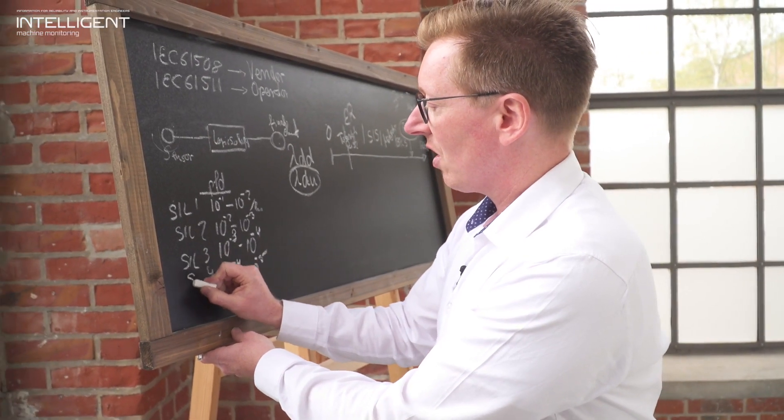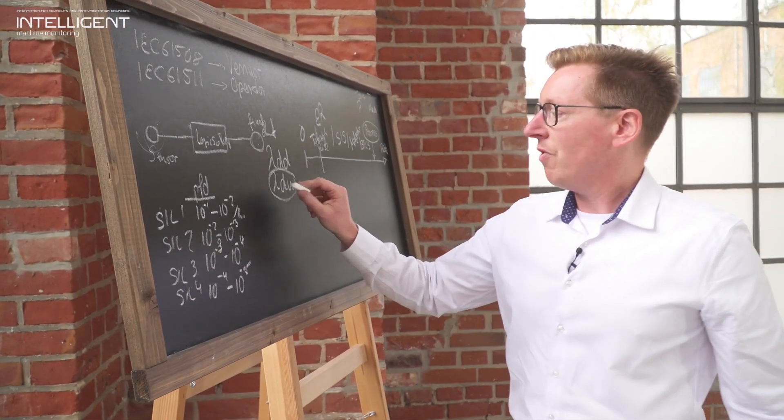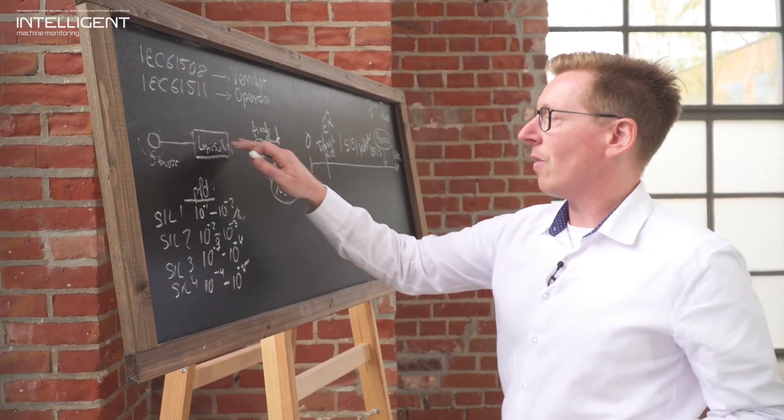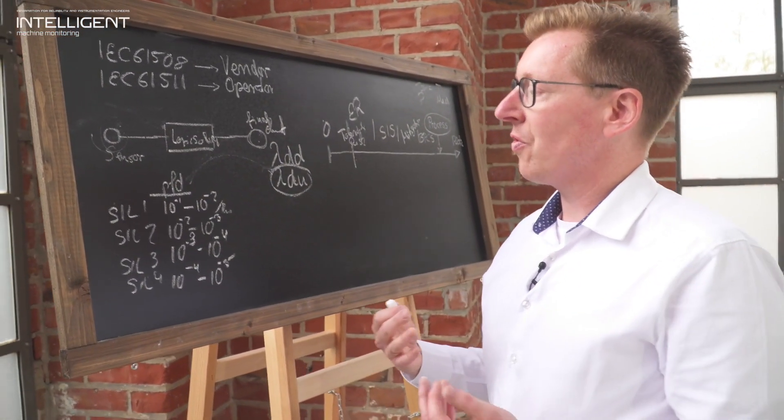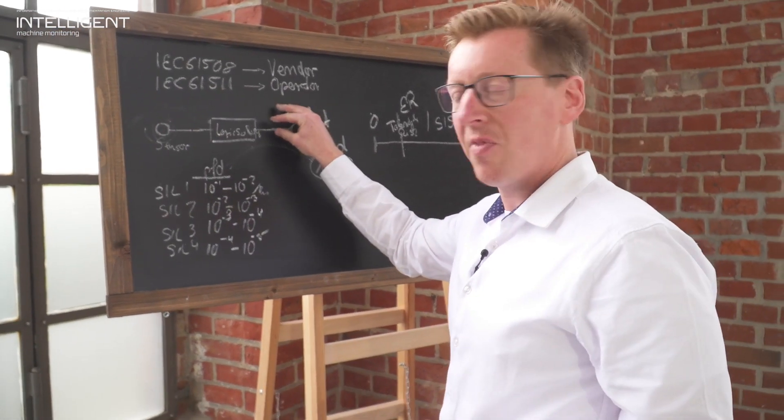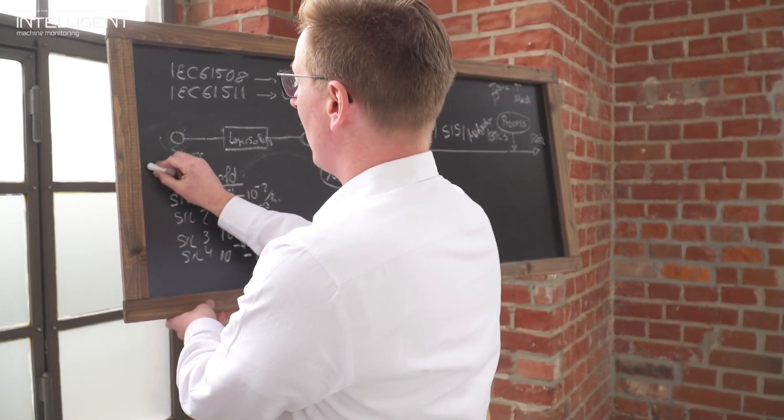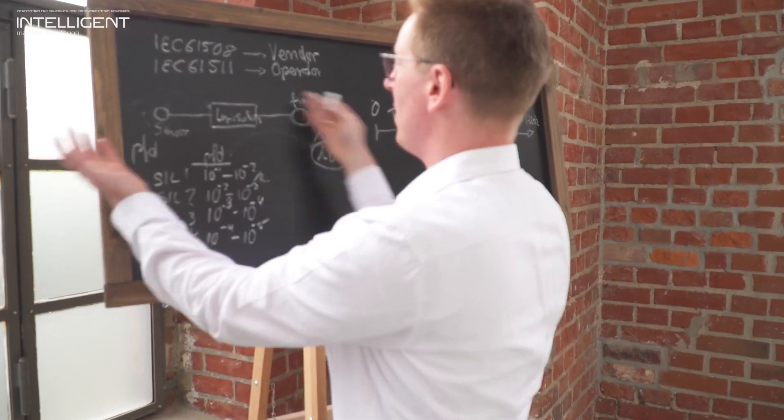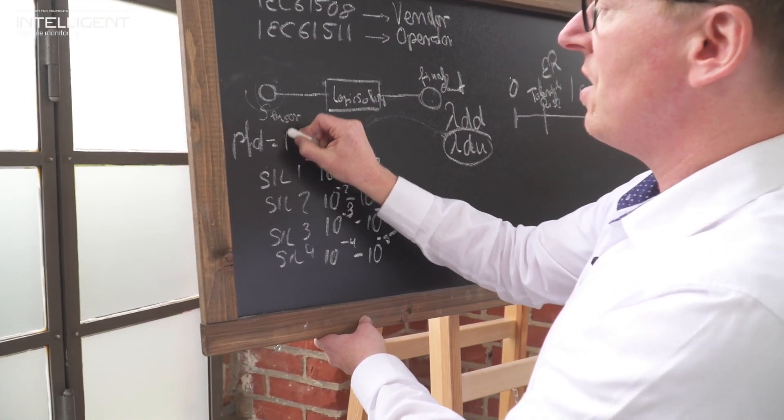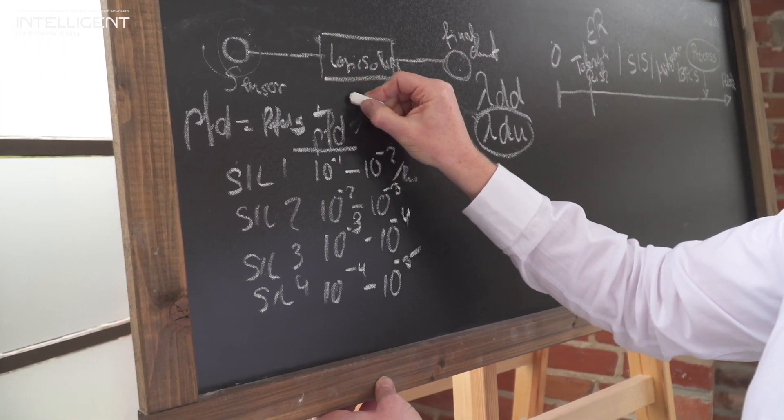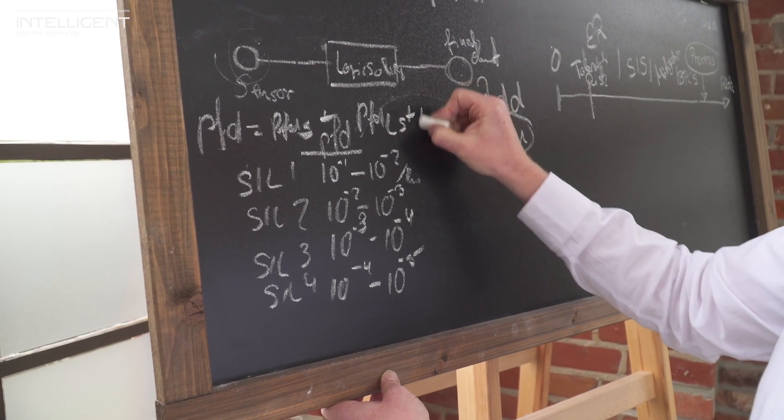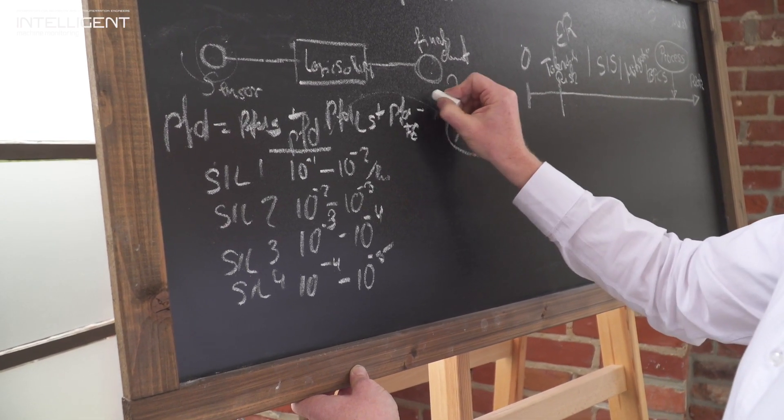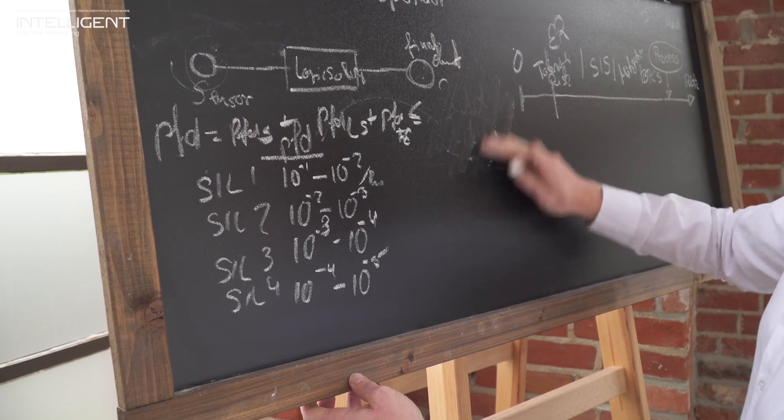And this lambda DU value is the one driving this PFD value. When you do the evaluation of your SIS system, it is not sufficient that, for example, you require a SIL 2 system. When you have a SIL 2 requirement, you have to calculate the PFD of the entire chain of command, the entire PFD across the system. So that includes the PFD of the sensor, plus the PFD value of the logic solver, plus the PFD of the final element. And this needs to be below your SIL requirement.